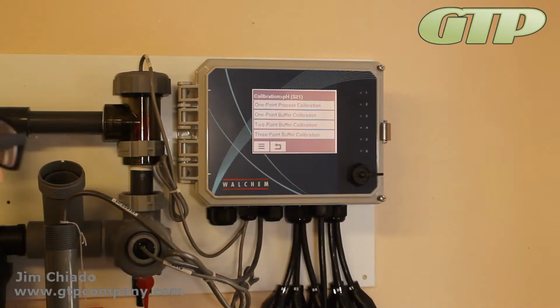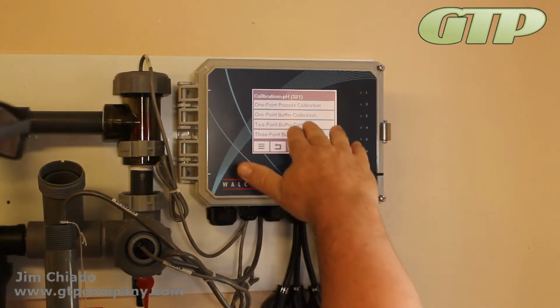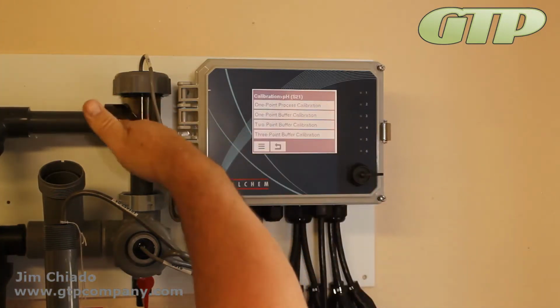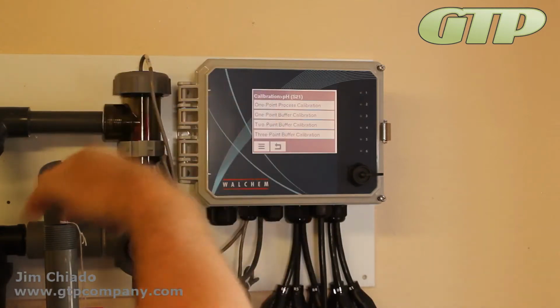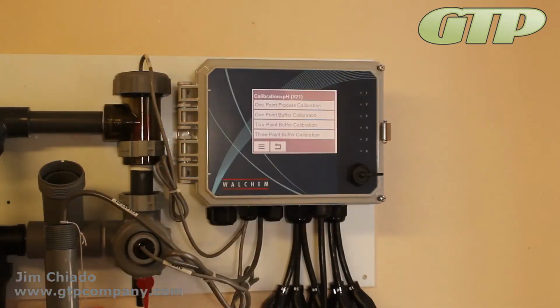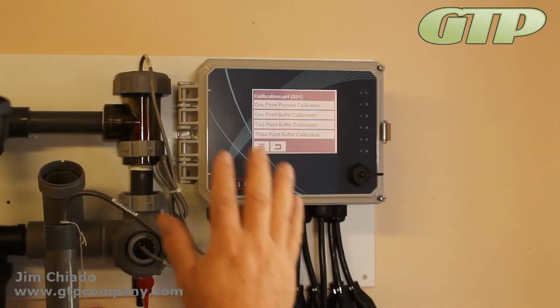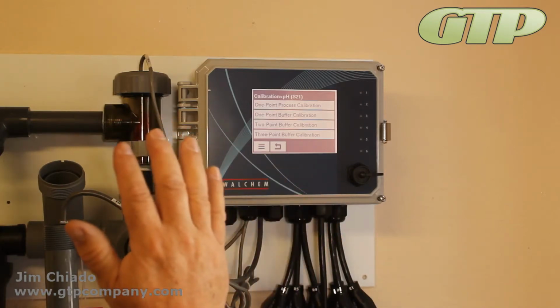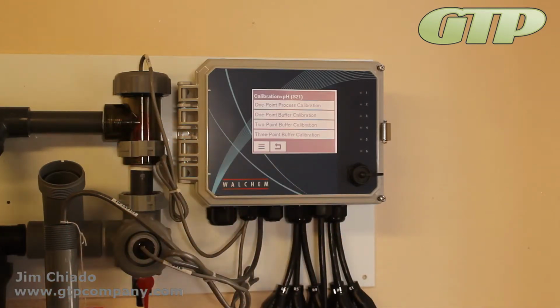Now in calibration, they do allow you to do a 1-point process or a 1-point buffer. Still, again, I don't really recommend it, because even if you're just doing a 1-point process and you're telling it this is 8 all the time, it's not fixing the 0. It's not putting the slope in there properly. You really should do the 2-point. Okay, if you're in a pinch, it can work. If you're doing pH and you're going to a place that has pH, please have 2.